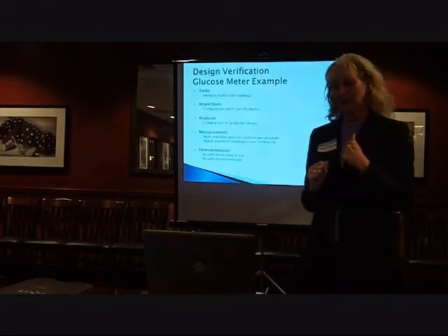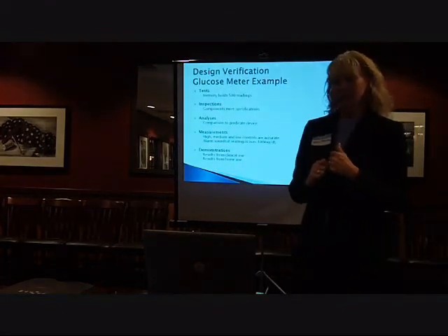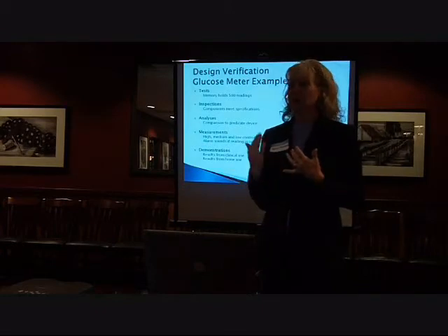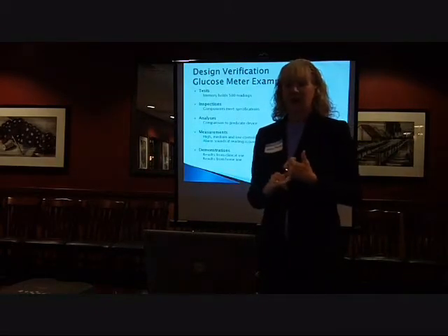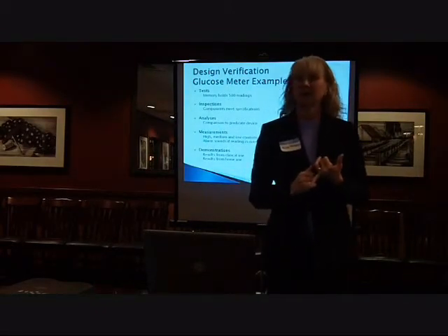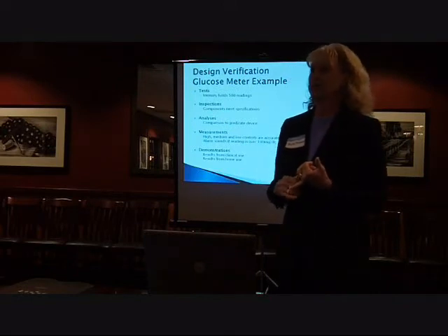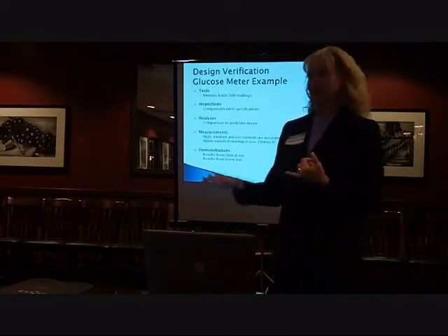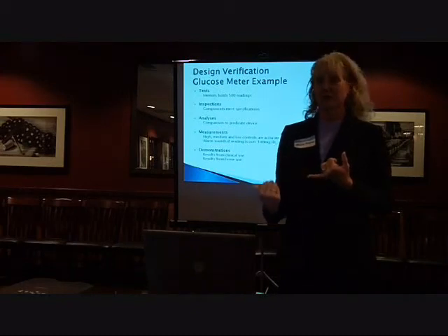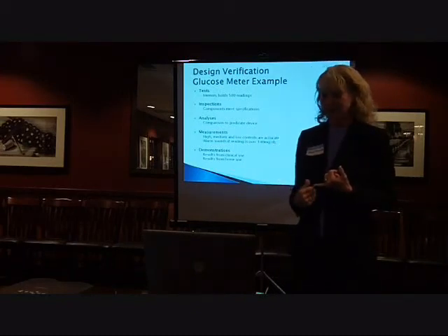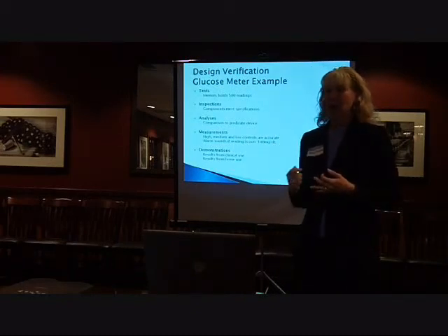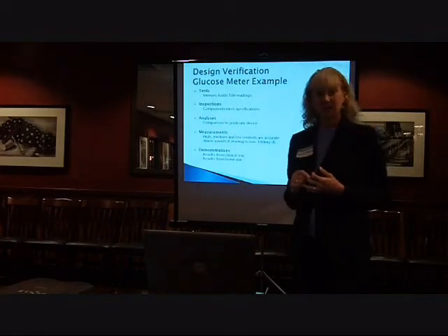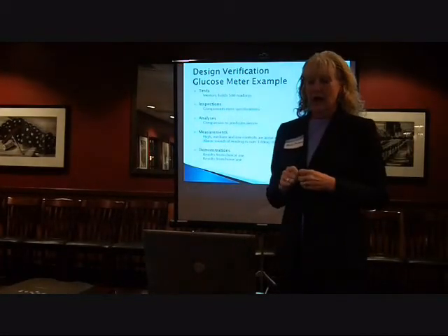But going back to our example, we see that through verifying this, the memory does hold 500 readings. Of course, you're going to have to challenge it and try to put in a 501 and see if it responds the way that you have written it up in your requirements. The individual components meet the specification coming in.